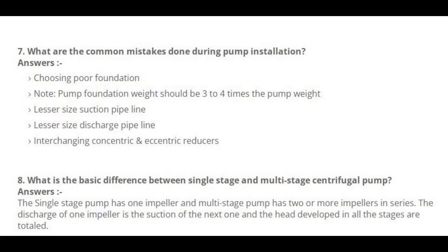Number 8: What is the basic difference between single-stage and multi-stage centrifugal pump? The single-stage pump has one impeller and the multi-stage pump has two or more impellers in series. The discharge of one impeller is the suction of the next one, and the head developed in all the stages are totaled.